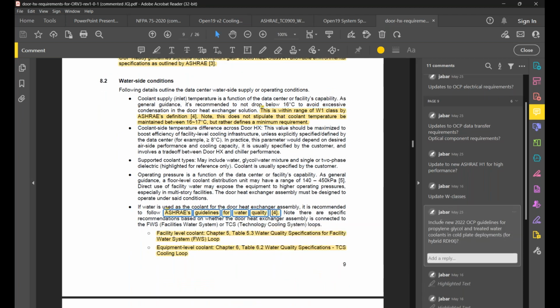In terms of ASHRAE guidelines for water quality, we do have this. We also have a recently released OCP guideline - it's more for cold plates, but it does talk about treated water. We probably need to add in here that this is now a new document to reference, especially if you have a hybrid deployment of a cold plate with a rear door heat exchanger, and they're both integrated. You need to use the more stringent of the two to specify your fluid quality requirements. So that might be another thing we need to add in here.